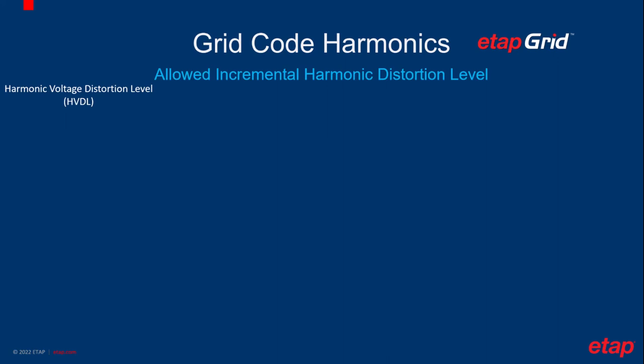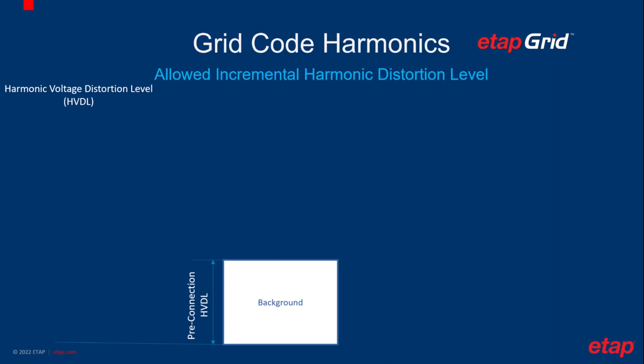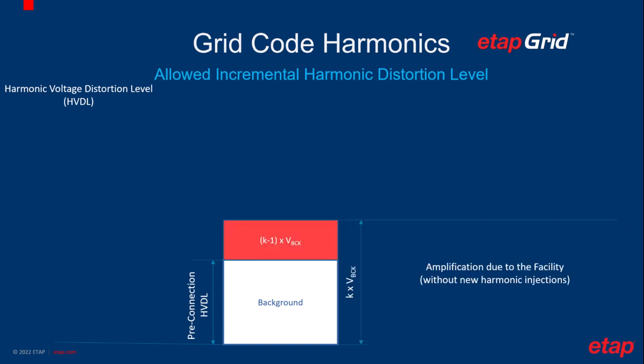Now let's talk about what the incremental distortion level is. Before the new installation is connected, there is only background harmonic distortion, which was measured by the TSO, as we mentioned earlier. And there's a power grid equivalent impedance. When we connect a new facility impedance to the power grid, the total impedance seen from the PCC gets changed. This new impedance will have an amplification effect on the background harmonic voltage source.